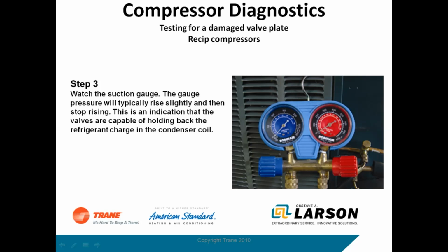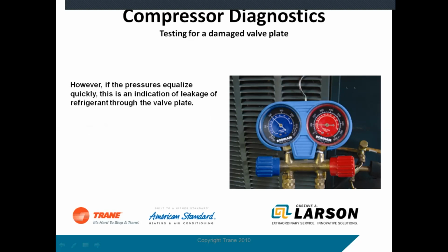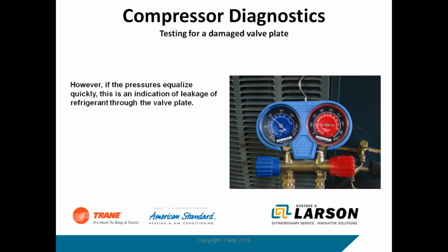So you'd put your gauges on, close the discharge valve, and pump the unit down. And if it was good, it wouldn't leak through the valve plate, and it would hold vacuum. And that's how you did a valve plate test. That also tested your high side and your low side. So if the compressor had the ability to pump it down, that meant it could pump against a load. And it also meant that the valves were working properly.